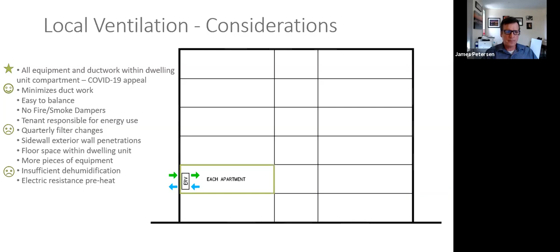In this case, you have a piece of equipment associated with ventilation for each apartment. An example of that being onerous is that it's another piece of equipment that has to be serviced, compared with a central system. The Finch job, for example, had two dedicated outside air systems on the roof. If you go this route, you have many pieces of mechanical equipment, and in this case we're not able to mechanically dehumidify the air with this approach. That's unfortunate, and it's a shortcoming of local ventilation.